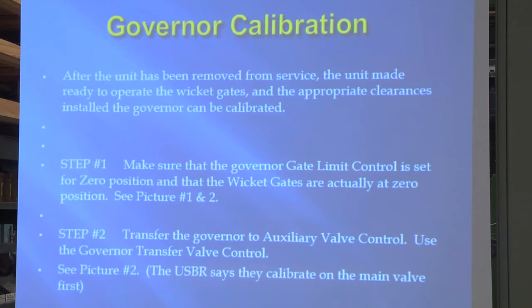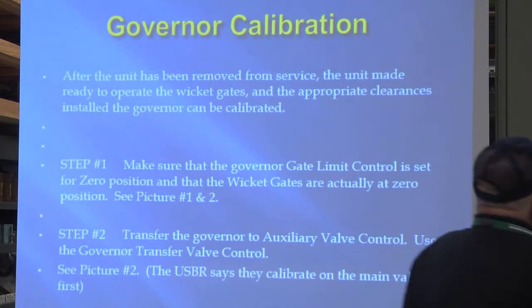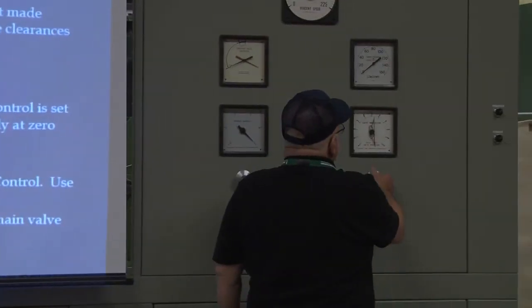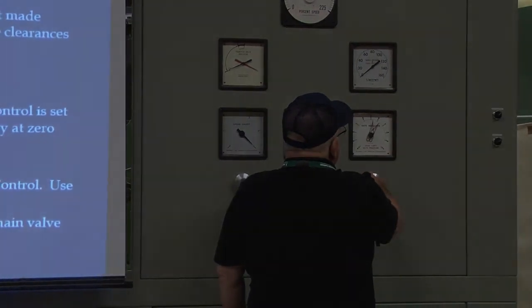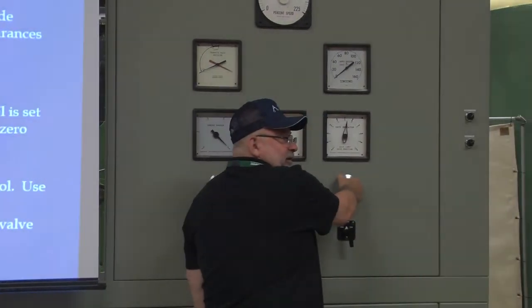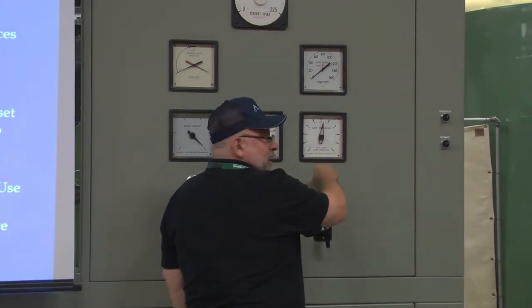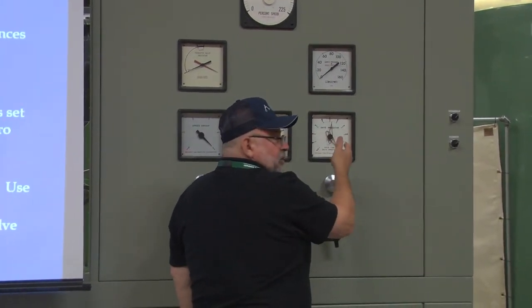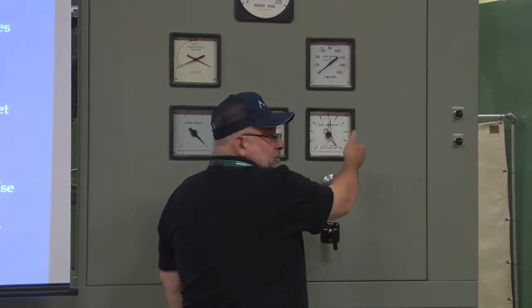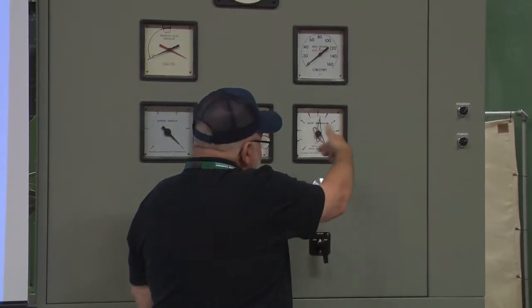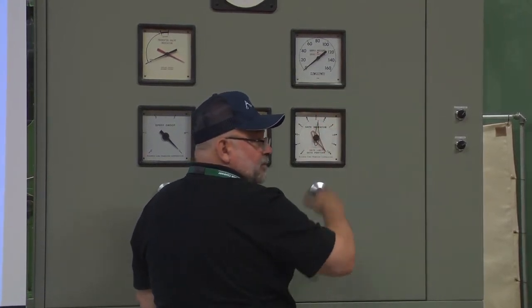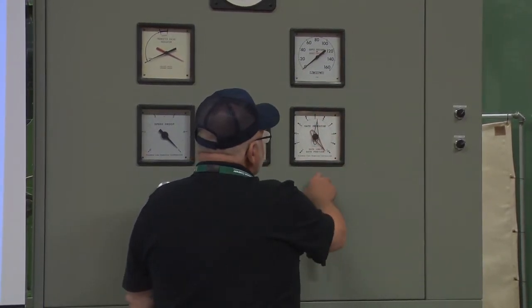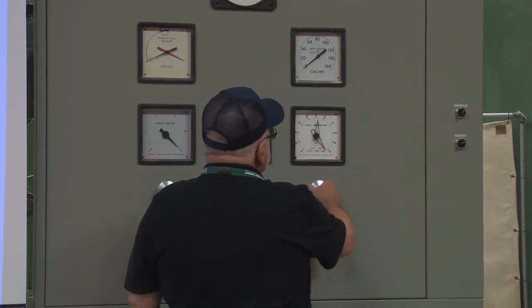Step 1, make sure the governor control gate limit is set for 0 position. Anytime you walk up to a governor and it's down and you're going to do something on it, you want to make damn sure that gate can't move. I've seen guys calibrating, wanting to see the whole stroke, and then they come over and do something else, and somebody gets pinched in there where it's moving. You don't want to hurt anybody. You can't do any of this when anybody's working in the spiral case. It's got to be closed and locked, okay?